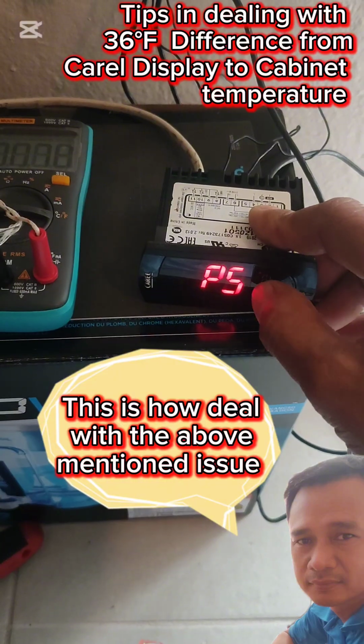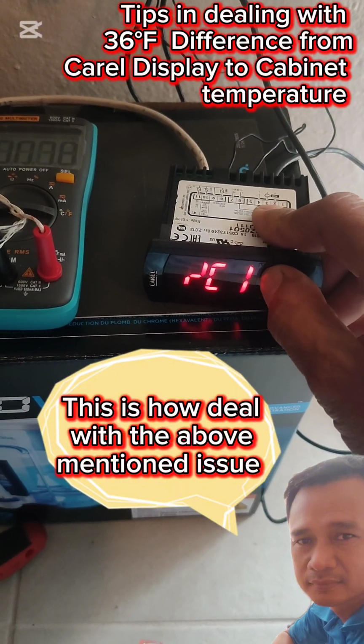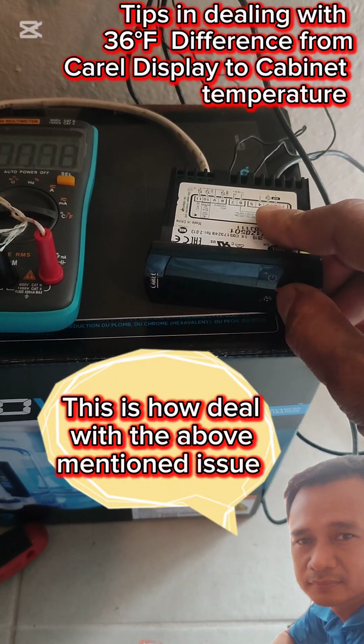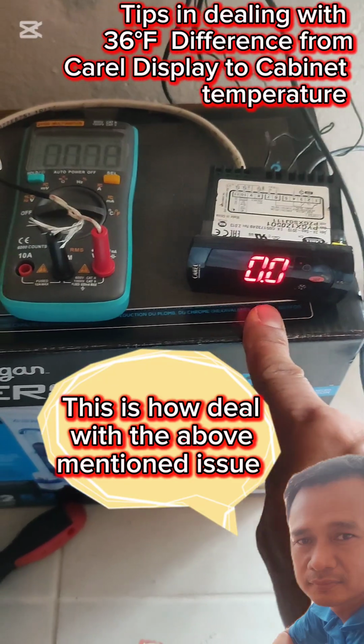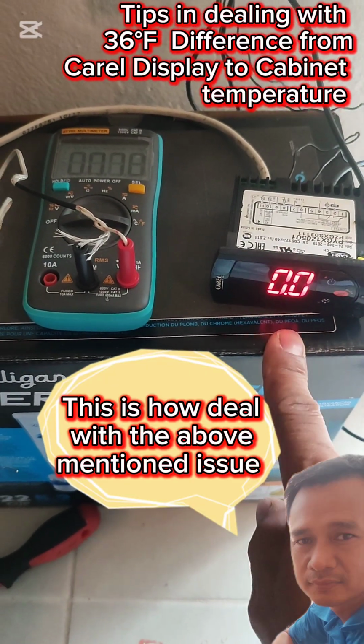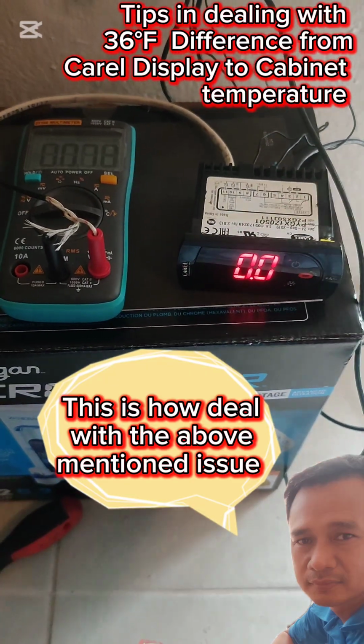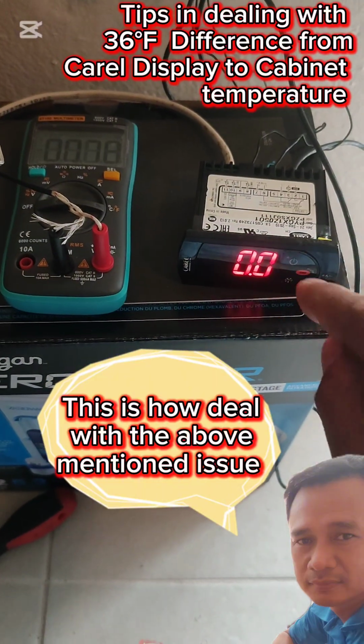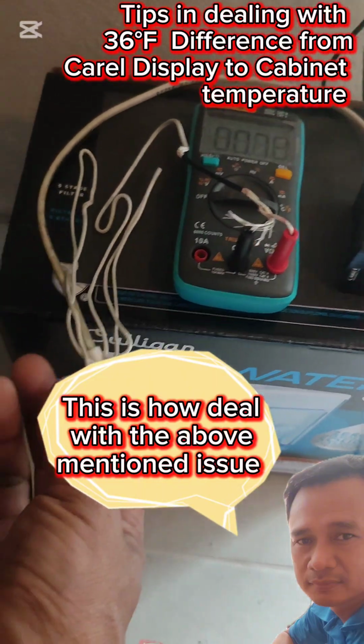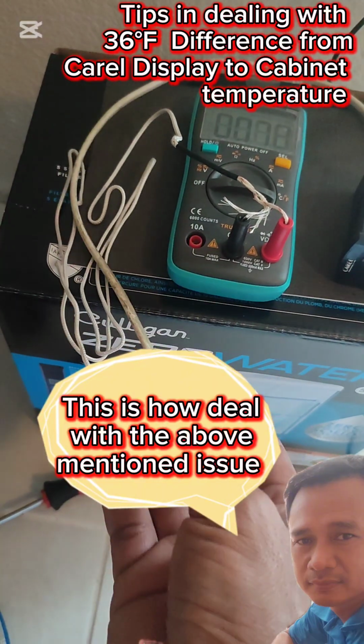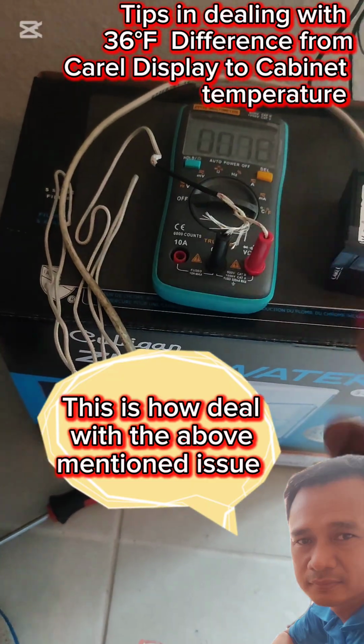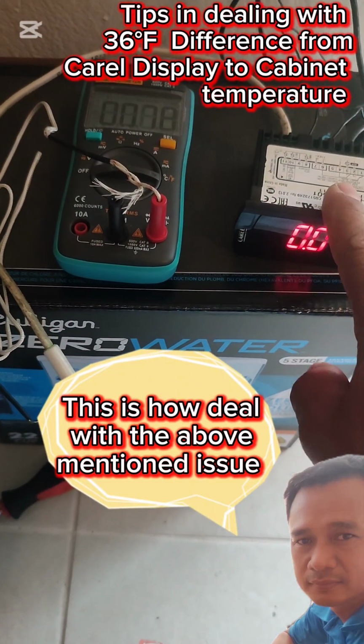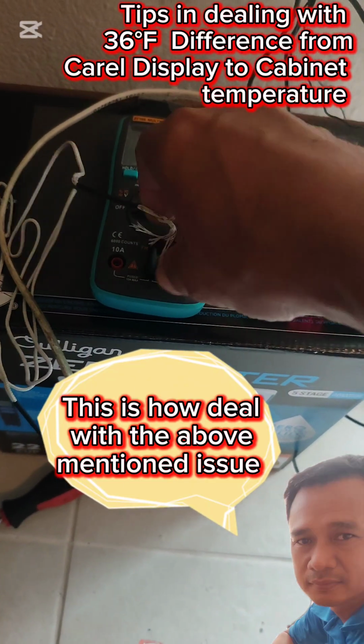Then press set, and let's locate /C1 here. So it's set to 00. We're not going to calibrate this. Instead, we're going to exit that, and I'm going to replace the sensor, and I'm going to show you what's faulty here, why we have a difference, 114 here and 78 here.